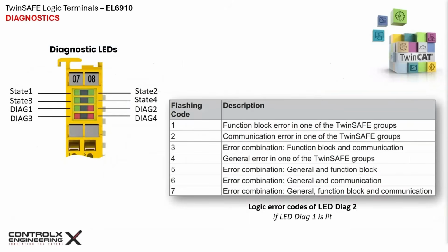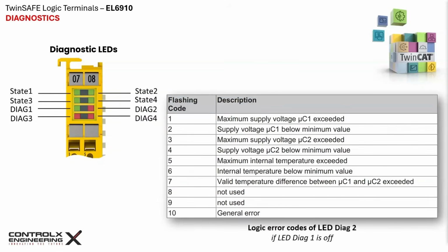When the diagnostic 1 green LED is lit, the error code is determined by the number of flashes of the diagnostic 2 LED. This table lists the possible flashing codes and their descriptions. These are usually not serious issues and are related to problems with the logic implementation, communication errors, or function block related errors. This table lists the possible fault states when diagnostic 2 is flashing and the diagnostic 1 green LED is off. As you can see, these faults are more serious and related to voltage and temperatures not being within valid range.